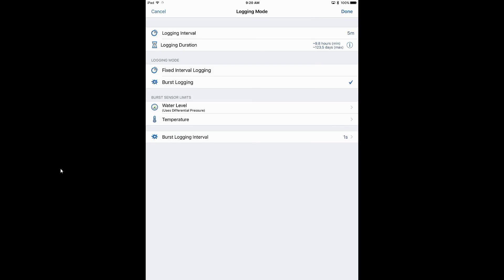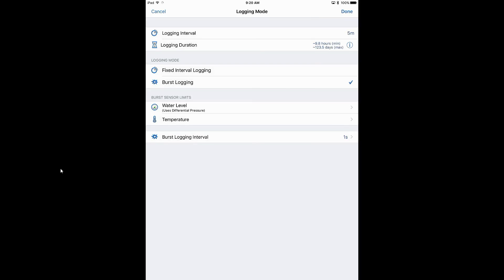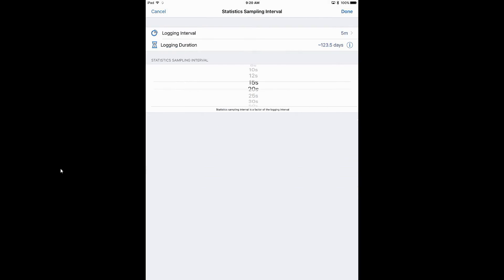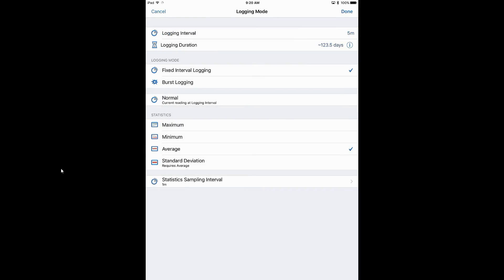The other logging mode is statistical logging. For example, if we uncheck Normal and log at a five-minute interval, then select average statistics with a one-minute sampling interval, each five-minute measurement will be based on the average of five one-minute samples. For this application, we're just going to use normal logging — we just want that five-minute snapshot of data.